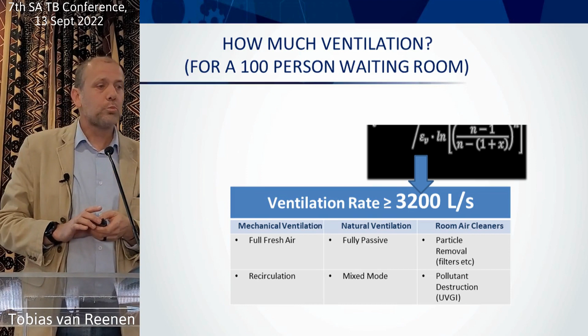I don't know if we've agreed, but I was hoping we came to an agreement that waiting rooms are very high risk. However, dilution ventilation alone cannot protect against long-term exposure. You might have noticed in that formula there's a little t, that's the hours of exposure. And also our tolerance for risk for the general population using a facility versus the healthcare workers, based on regulations among other things. The tolerance for risk for healthcare workers is much lower than for users of that facility, and the exposure time is much more.